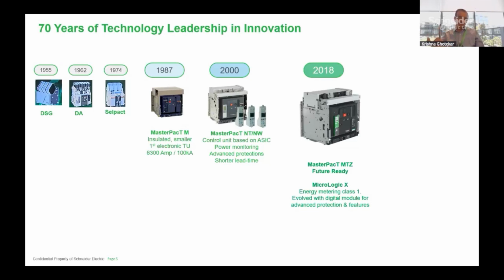this was used mainly for critical applications like data centers, hospitals, premium buildings, some projects. So wherever you need high-end features, power quality monitoring embedded inside the circuit breaker, more digitization, connectivity, wireless connectivity, or a communication protocol like Modbus, Ethernet, IEC 61850, and so on, we had that with MicroLogic X.